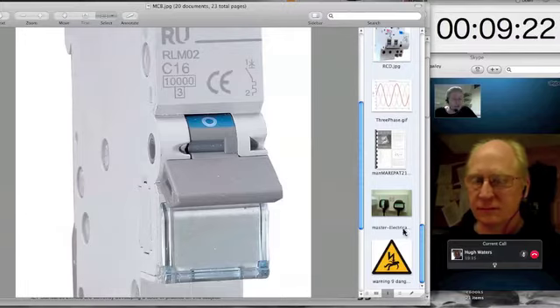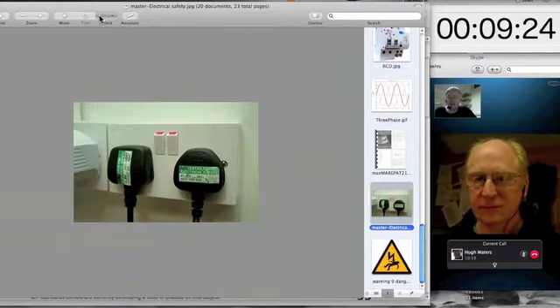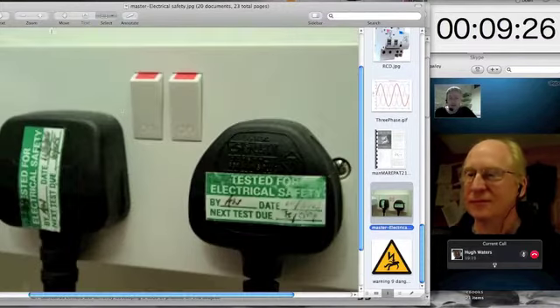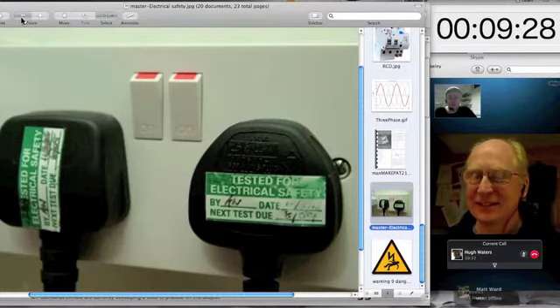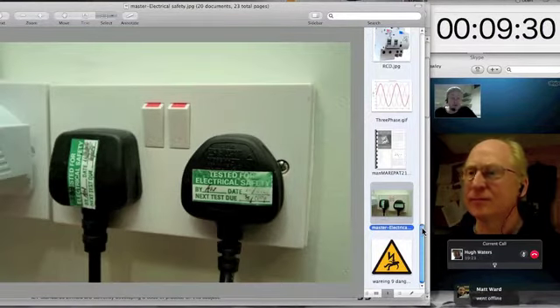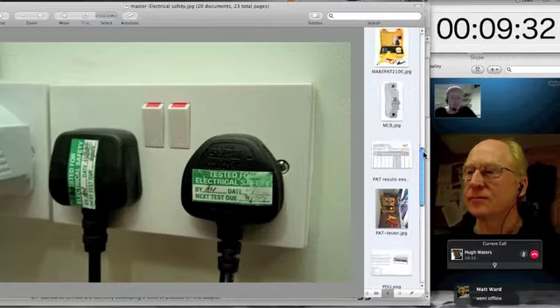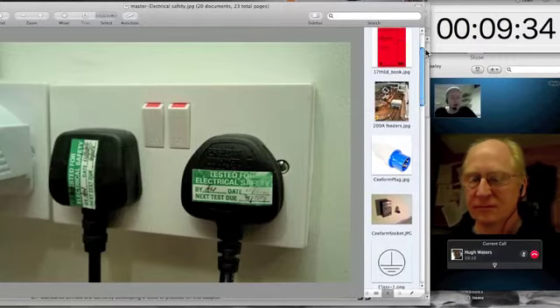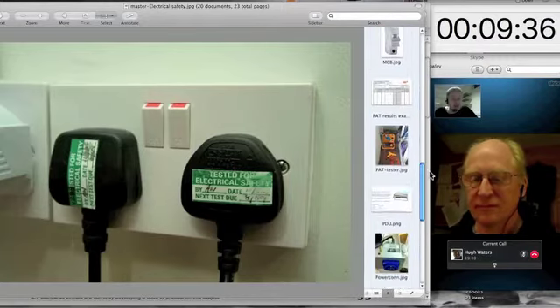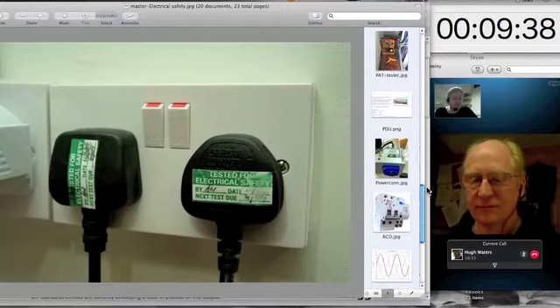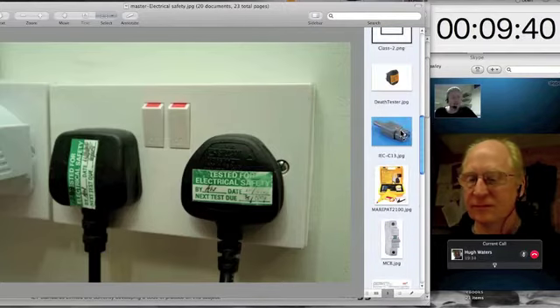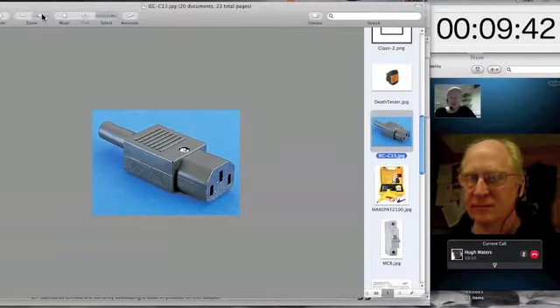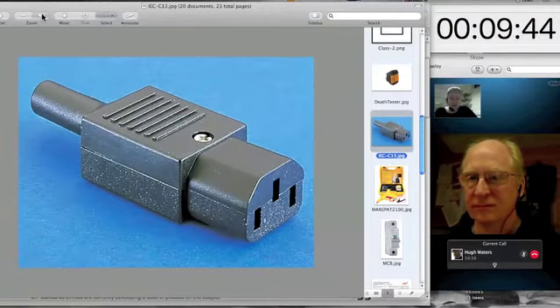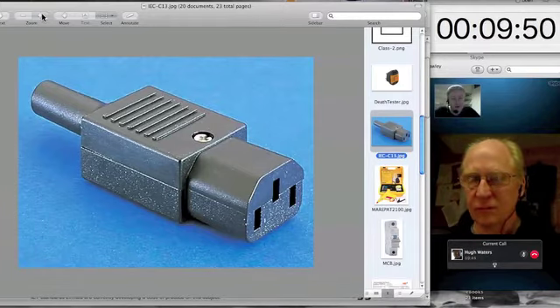But even if it isn't, so I've just popped up a 13 amp mains plug just for illustration. But even if it isn't being powered off a 13 amp mains plug, if it's being powered off what we consider to be a technical distribution, off an IEC connector, sometimes referred to as a C13 or a C14 connector, which is a 10 amp connector, which is kind of specific to broadcast and IT, you'd expect that connector to have a fuse in the distribution board at the top of the cabinet. So there'd be a fuse in the way.